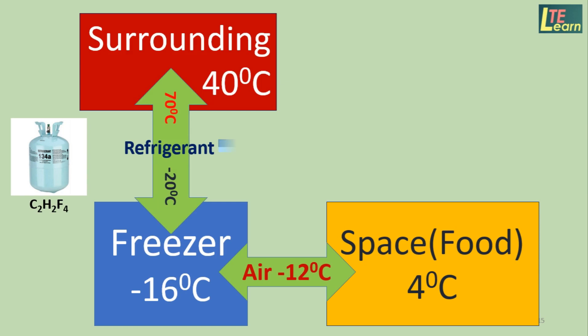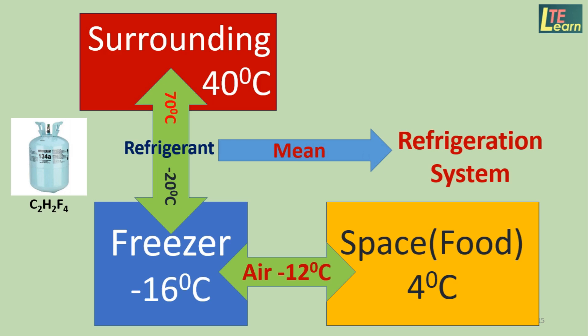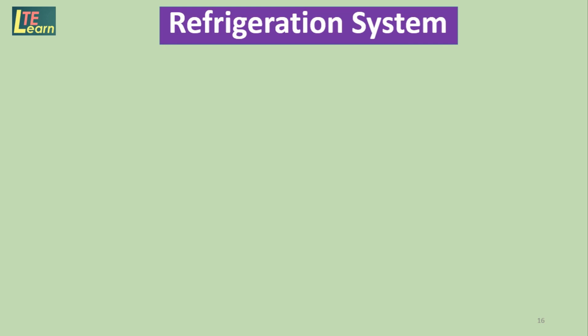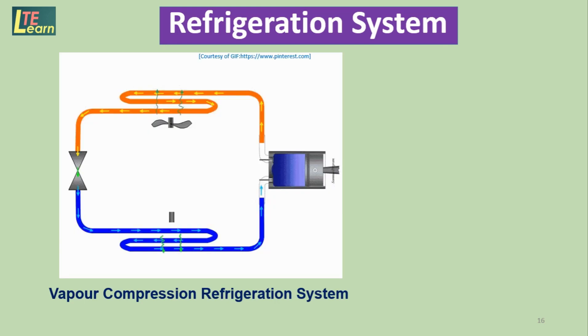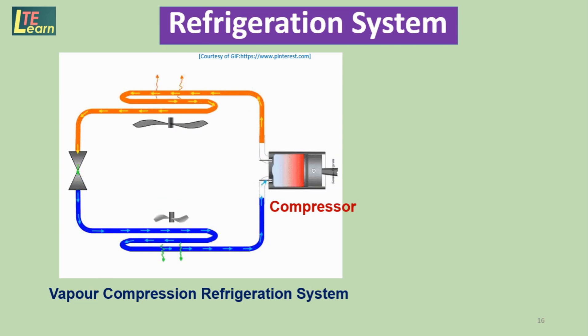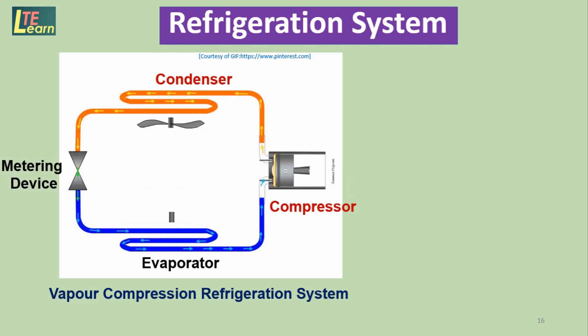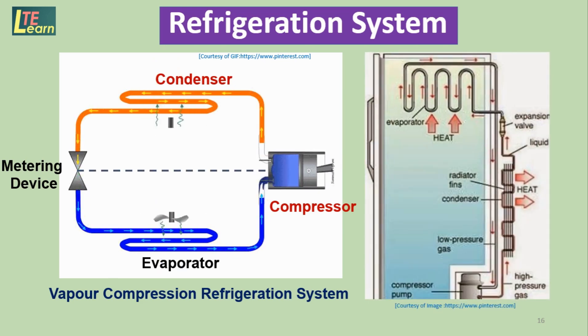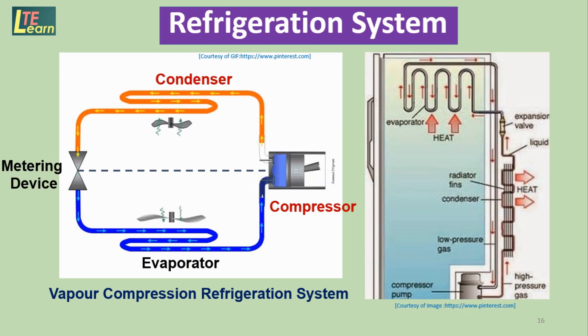So we now understand that the heat from the food to be cooled is taken by the evaporator and transferred using the refrigerant to the surrounding. This is done by the system in the refrigerator called the refrigeration system — specifically the vapor compression refrigeration system. It has four components: first, the compressor; second, the condenser; third, the metering device (expansion device); and fourth, the evaporator. Above the dotted line is the high-pressure and high-temperature region, and below the dotted line is the low-pressure and low-temperature region — heat is absorbed at the evaporator and rejected at the condenser.